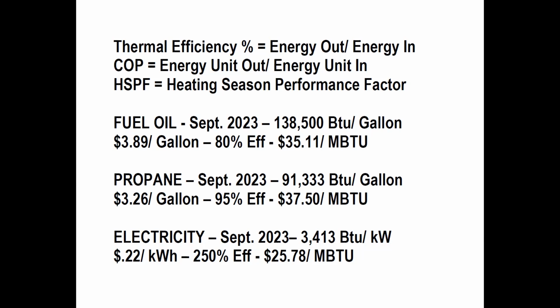And the website that I gave you before is going to assume an 80% efficient propane furnace. Nobody's installing 80%. If they are, they're nuts. The condensing propane furnaces will get you 95% efficiency. And that's because, back to the phase change thing, they run the temperature of the products of combustion down to 130 degrees where it actually makes water. So any new boiler or furnace that's used with propane will have a condensate drain off of it, because you want it to be condensing the products of combustion into water. It's still got CO2 going out, but it's also got water that's being ejected.